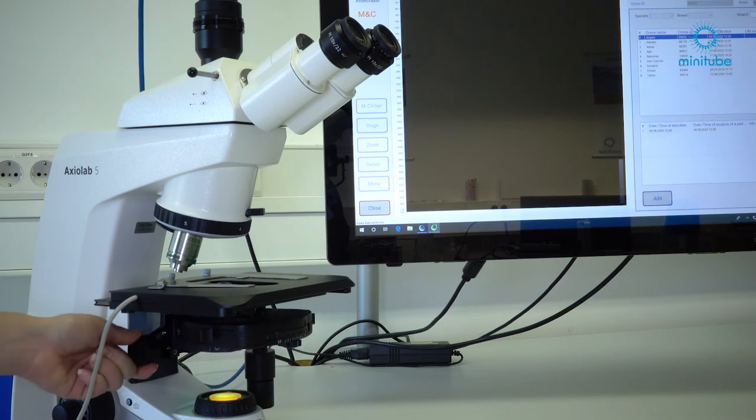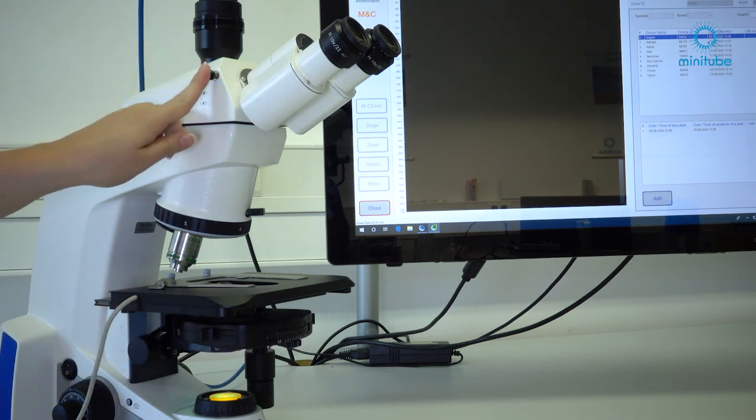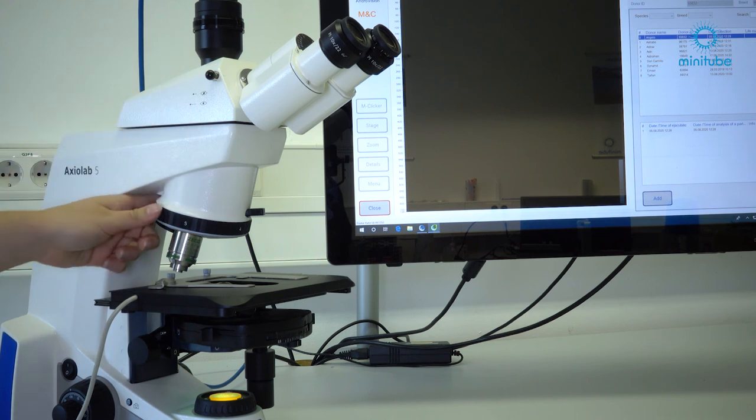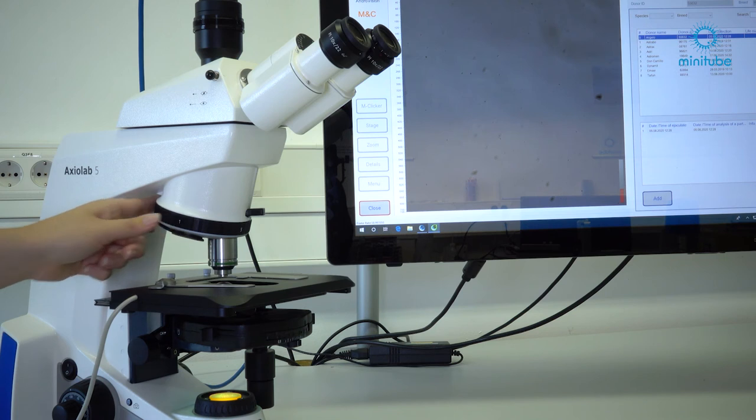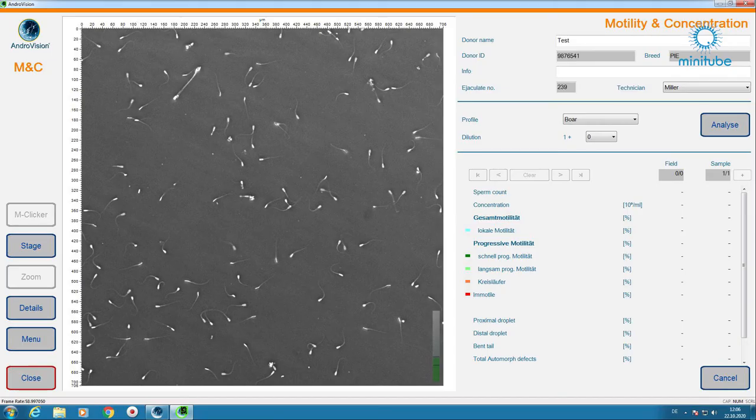Check if the switch between camera and eyepieces is at the right position. And check if the right objective is swiveled in correctly. The label of the objective has to fit to the label of the condenser disc.